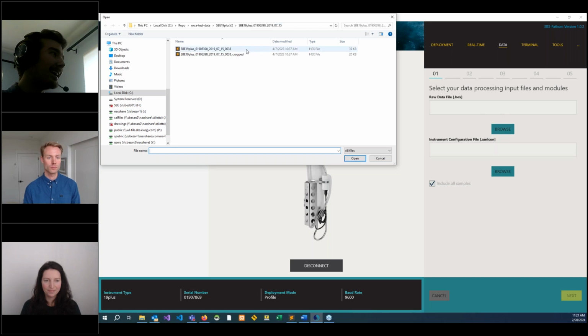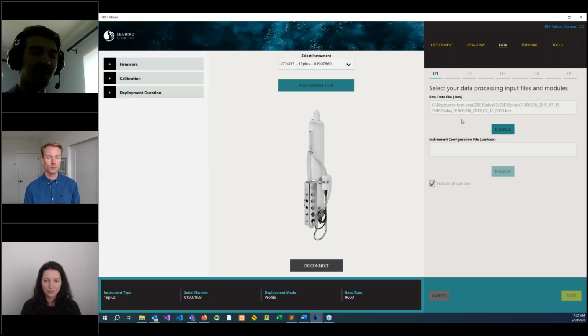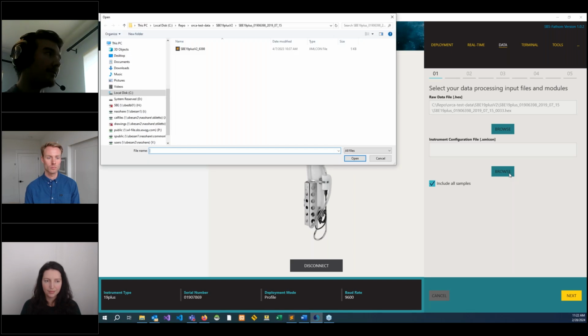We're going to load in some data from a different 19 plus profile that is more interesting, that we can look around with and play with a bit more. We're also going to load in an XMLCon file associated with that instrument. Many of you might be familiar with XMLCon files. They tend to contain the calibration coefficients for our instruments. Sometimes the hex files will have calibration coefficients, but the XMLCon file is generally more of a source of truth. A lot of times Seabird will be providing those for you.